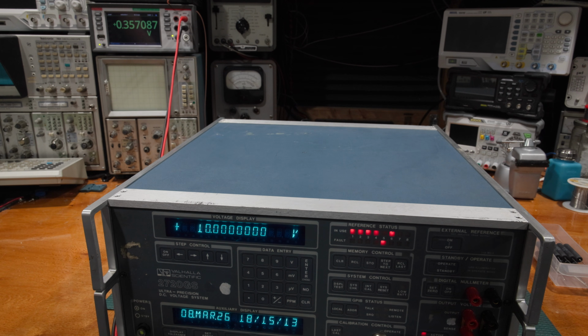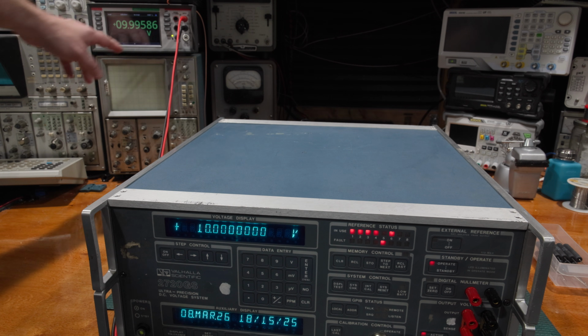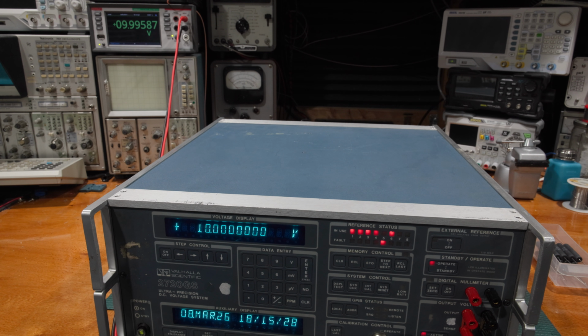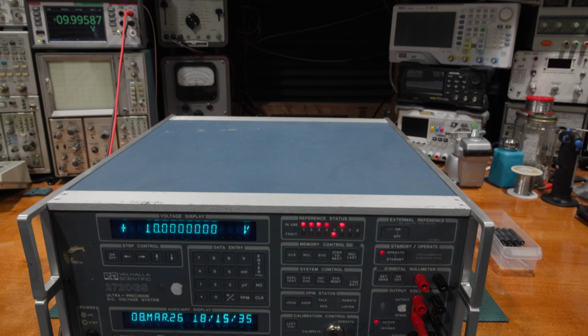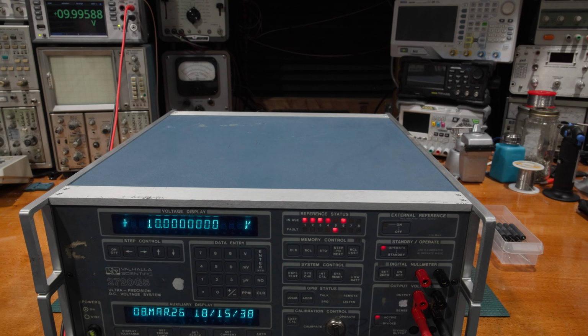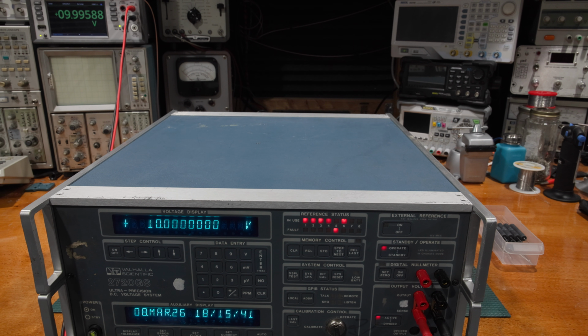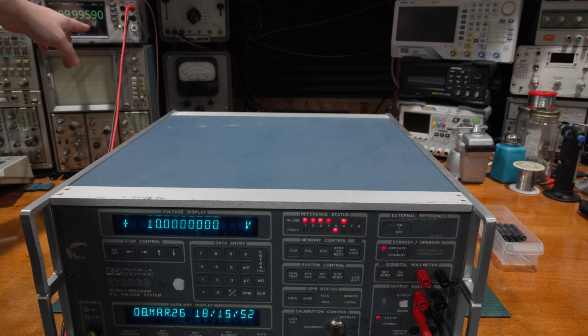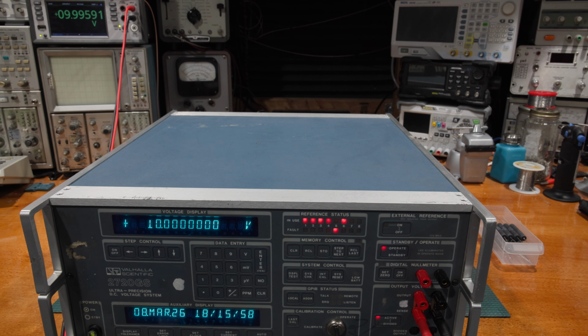All right, this meter is not warmed up, not powered on at all, but we'll ask it for 10 volts. And we'll kick the output on. Much better than before, especially considering that this meter's cold. So that's about as good as we can make it right now. What I need to do is move it back over to the shelf, because this one sits down there in the lab. And we'll really let the null meter compare it to the 434, which was way off in orbit, hundreds of millivolts. And this says we went from hundreds of millivolts to ones of millivolts, which is good.